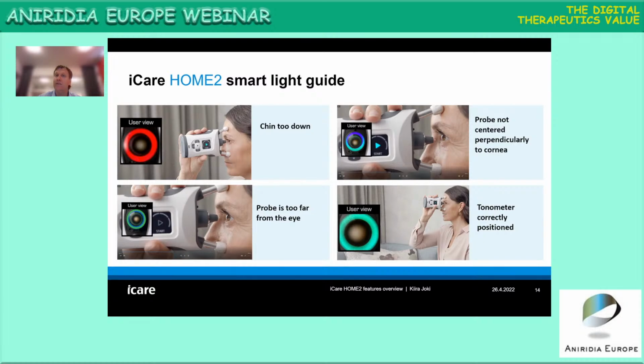If you see blue upward or downward and green in the other part, it means the probe is not centered perpendicularly to the cornea. If you see a green ring and a blue ring, it means the probe is too far from the eye. And if you only see green, the tonometer is correctly positioned for you.